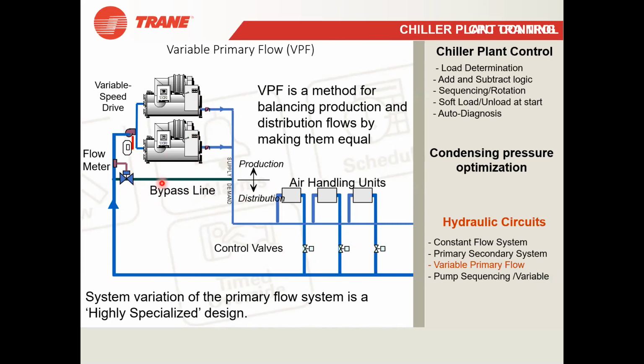This is a very critical, complex system. Controlling is difficult because all are primary. We don't have any secondary. If there is a secondary, then it is easier to control. So in this case, the primary pumps alone take care of the complete system flow requirement. These two primary pumps are taking care of the complete flow. So on the load side, whatever increase is happening also has to be taken care of by only the primary. And if any load decrease is happening, that also has to be taken care of by only the primary.